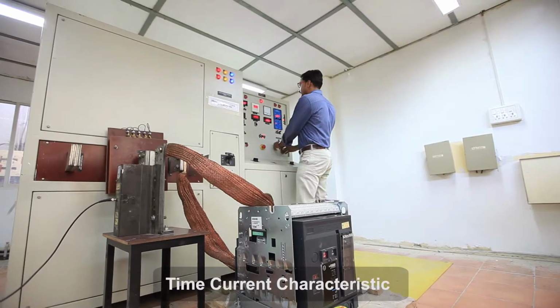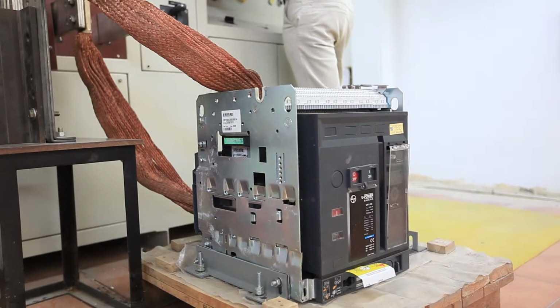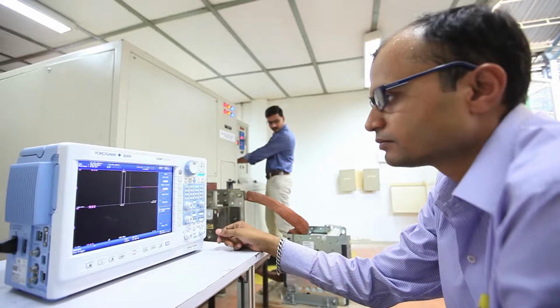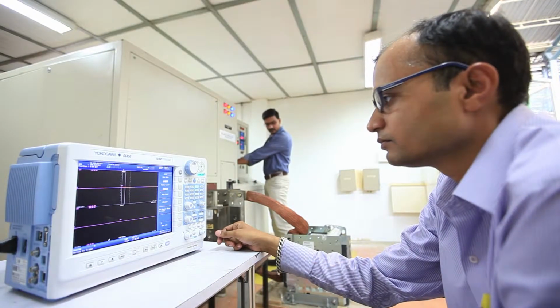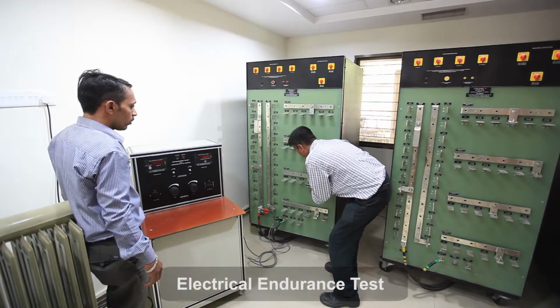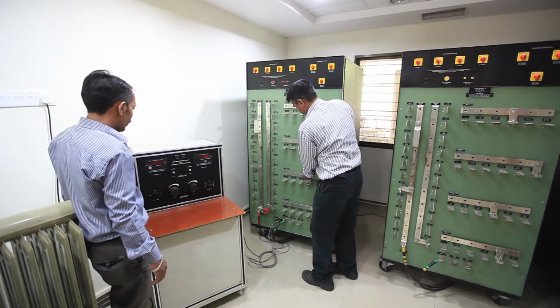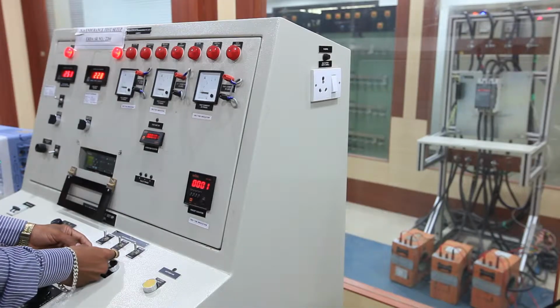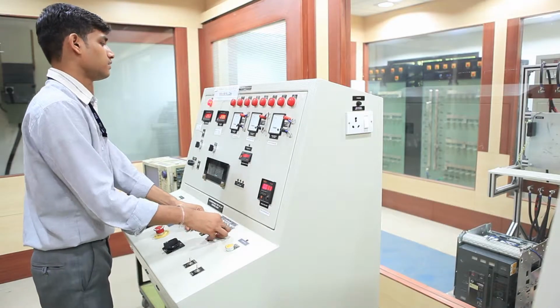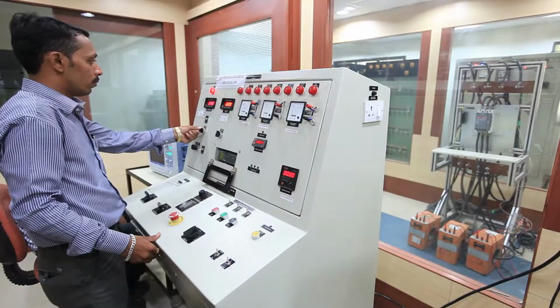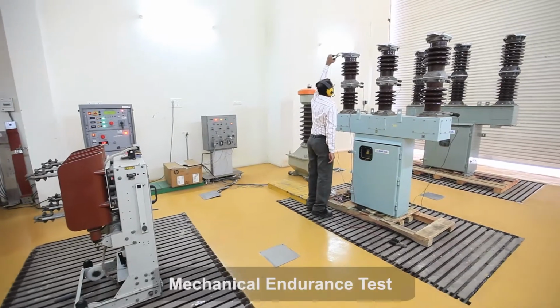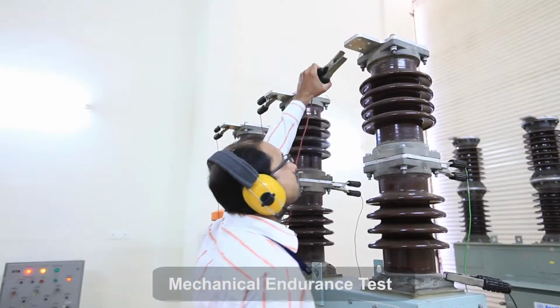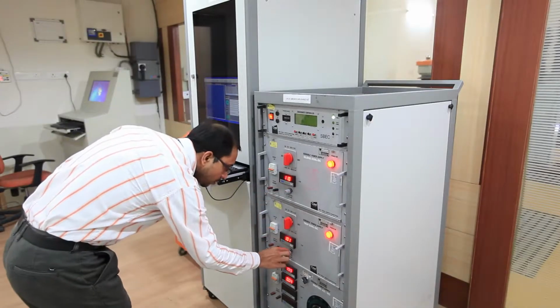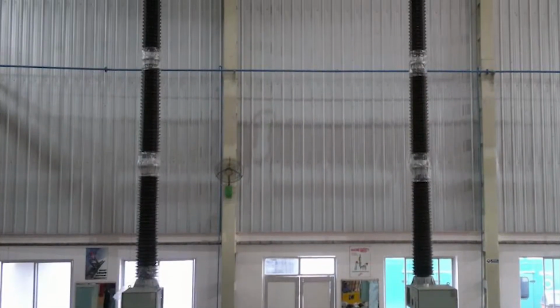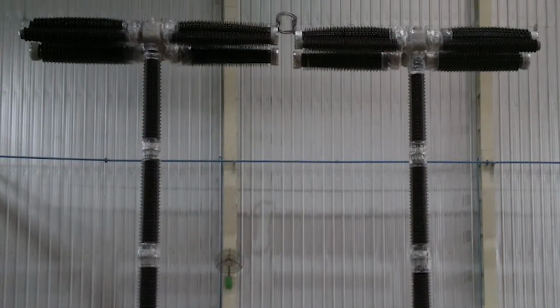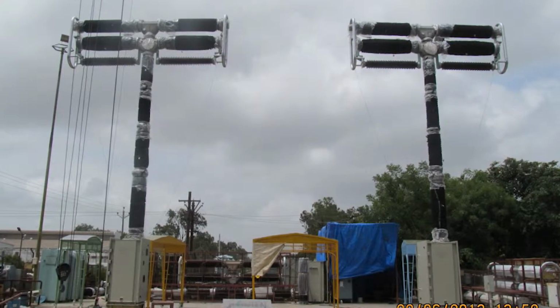This laboratory also has 4 feeder loading units for testing 16 outgoing units of distribution boards during temperature rise tests. The time current characteristic test on air circuit breakers and fuses are carried out to a maximum current of 40 kiloamperes. 6 test setups are available for simultaneous electrical endurance tests on MCCBs, contactors and ACBs up to 2000 amperes at 440 volts. We have 3 test bays for mechanical endurance test up to 33 kV circuit breakers. ERDA witnesses these tests on circuit breakers up to 800 kV at manufacturer's premises.